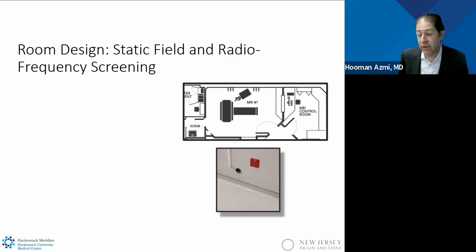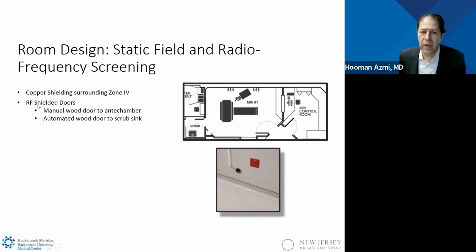In terms of satisfying the MR world, well, we had to have copper shielding in what's called zone 4, which is where the MRI is located. We have to have RF shielding for doors. The doors are wooden and they're specialty doors, and one is automated, the other one is not. Data links all need to be over fiber optic cables, and electric cables needed to be properly shielded.